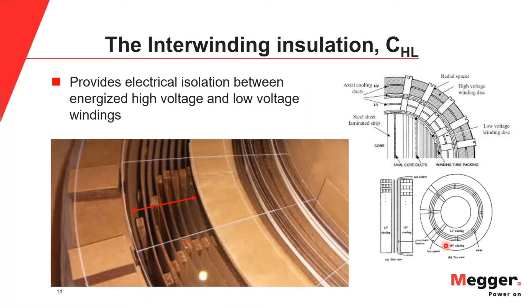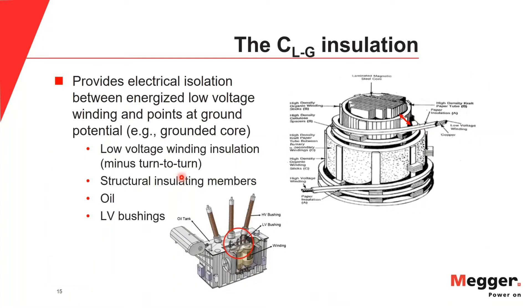CHL is called the interwinding insulation. It provides electrical isolation between energized high and low voltage windings, and is comprised to a large extent of paper. As a consequence, moisture in the transformer is attracted to this region since paper has such an affinity for moisture. You can see the pressboard barriers here, separated by winding sticks that create cooling ducts for oil to flow through that region.